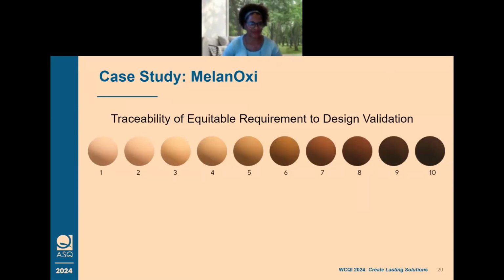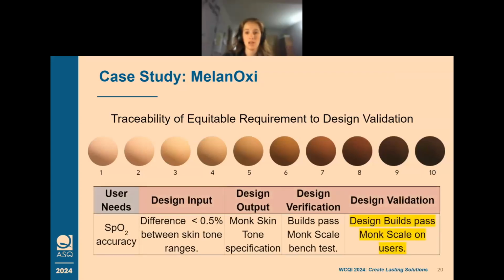So once again, here we have the traceability matrix for MelanOxi, and we talked about verification. We're now on validation, and this would be actually testing it on users. And just to reiterate how narrow the range is, how important it is that you consider your entire target audience and the impact of that. The science is narrow for pulse oximeters. 95% is healthy. 92% is you literally might have a misdiagnosis of peripheral cardiovascular disease. That's a real issue. So that 3% difference is a problem. If it's 3% off, that's literally the difference between somebody getting the treatment and the help that they need and that being completely missed.